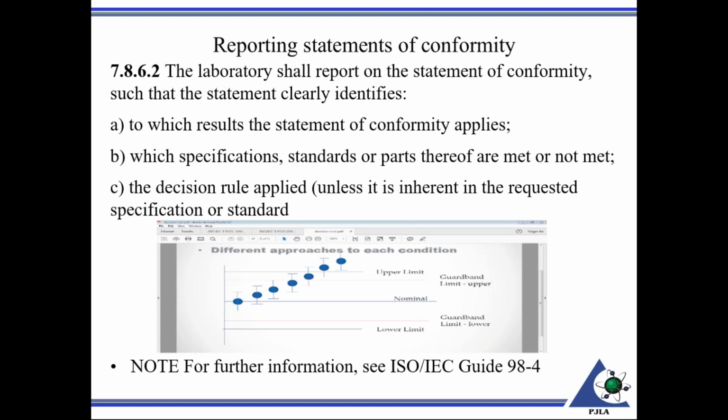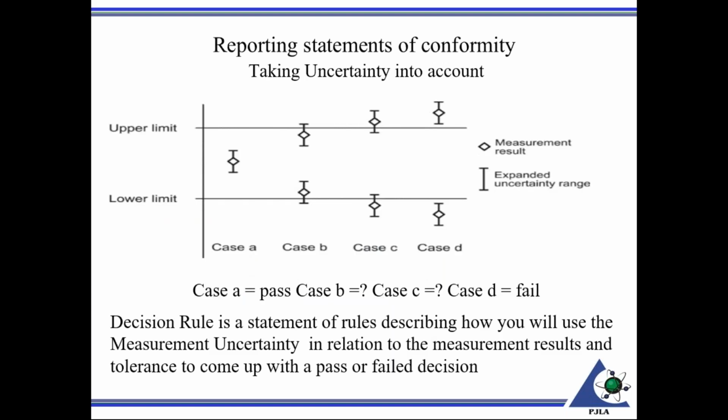I have, on the next slide, something a little bit clearer for you folks to look at. There we go. So here are several cases we have. The little diamond-shaped picture you have with the two end bars there, that's the actual, let's say, calibration results. And those little areas leading to the end bars, they would be the gray area, measurement uncertainty. And that's what that is, uncertainty.